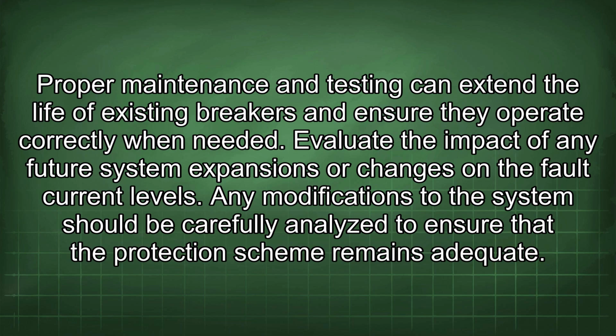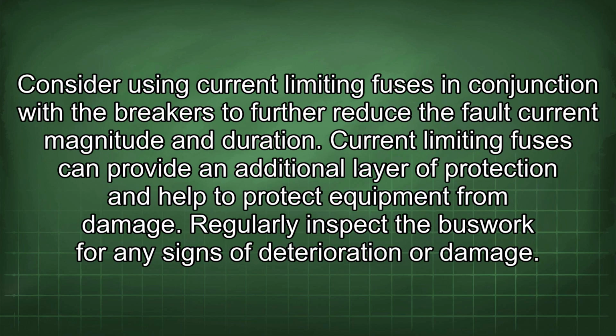Evaluate the impact of any future system expansions or changes on the fault current levels. Any modifications to the system should be carefully analyzed to ensure that the protection scheme remains adequate. Consider using current limiting fuses in conjunction with the breakers to further reduce the fault current magnitude and duration. Current limiting fuses can provide an additional layer of protection and help to protect equipment from damage.